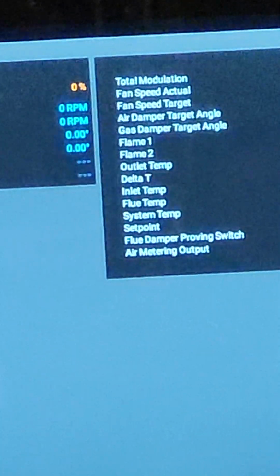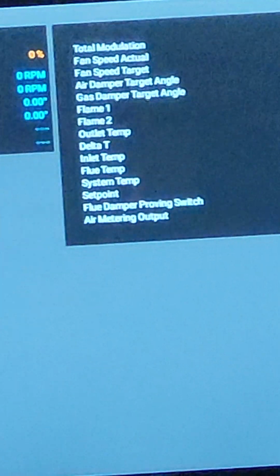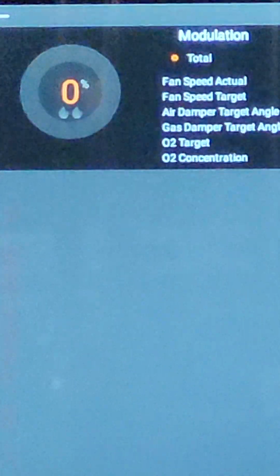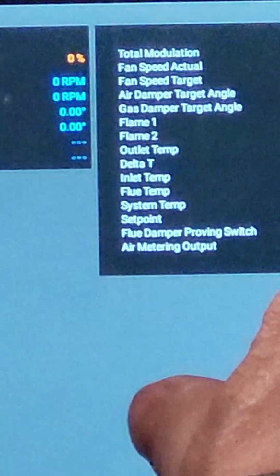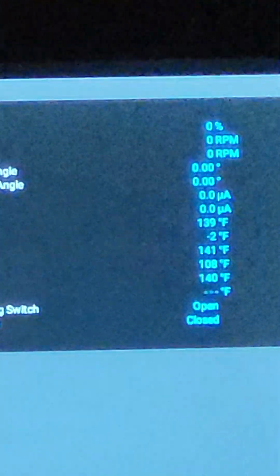There we go. It shows you the fan speed, actual and the target, just like on your main home screen, what we were looking at. It shows you the modulation, fan speeds, air damper, delta T, inlet temperature, outlet temperature. It also shows you the set point right there. So whatever he's sending, it's going to show you on that set point.